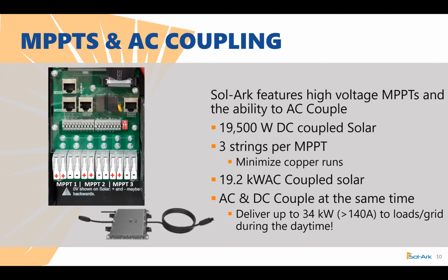And the voltage is actually going to be isolated between each unit. So it's fantastic. Maybe you have a different panel manufacturer and the homeowner's trying to piecemeal some parts together. Well, put it on separate MPPTs and that voltage difference won't matter anymore. Or maybe you just have an odd amount of panels. And so you'll build on MPPT 2 or 3 to a different value.